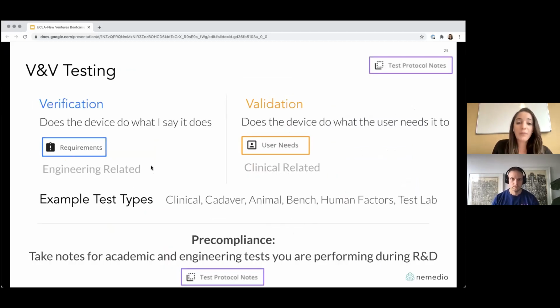So again, verification test: does the device do what you say it's going to do? These tests could be done in a test lab, or on a bench. One other thing to note is the tests that you do, you can't just say, oh, my device should weigh no more than 10 pounds, get the bathroom scale out of your house, put the device on it and take a picture of the weight. These tests need to be done with calibrated equipment.